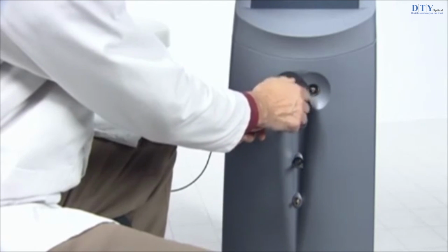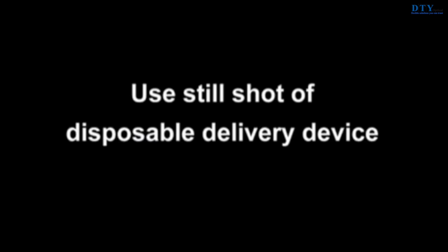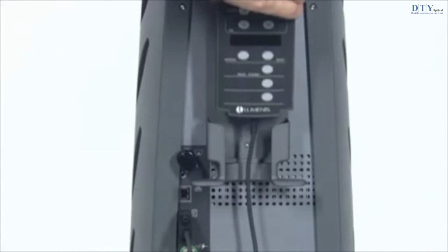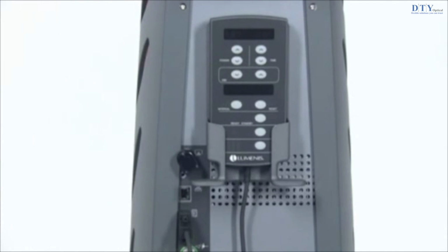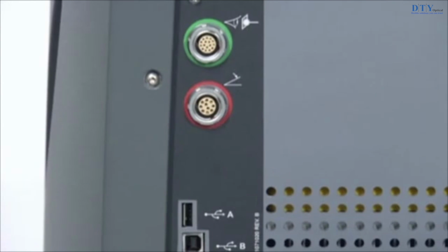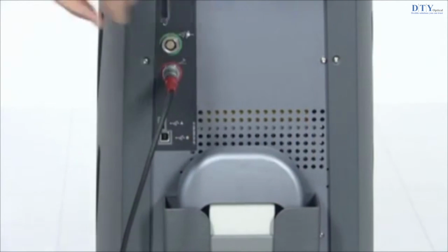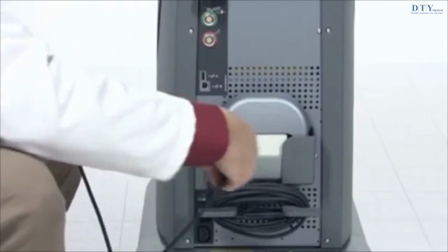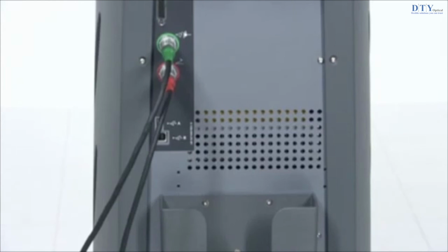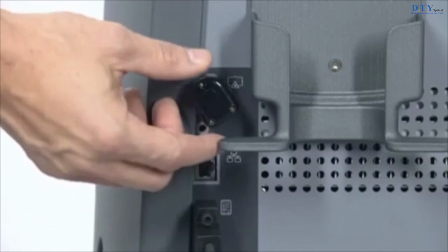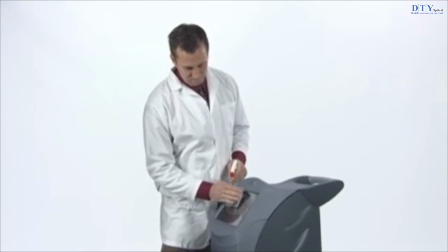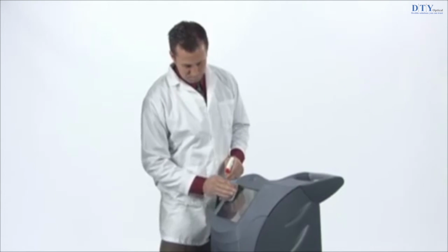Disconnect the delivery devices from the laser. If the delivery device is single use, dispose of it properly. Otherwise, inspect and clean the delivery devices, as instructed in the appropriate delivery device operator manuals. Store the remote control under the handle on the rear of the laser console. Remove the foot switch plug from the laser. Place the foot switch into the foot switch storage mount on the rear of the laser console. Wrap the foot switch cable around the foot switch storage mount. Disconnect the automatic eye safety filters, if used, and remove the eye safety filter extension cable or emulation plug from the laser. Disconnect the external door interlock, if used. Finally, clean the exterior surfaces of the laser as instructed later in this presentation.